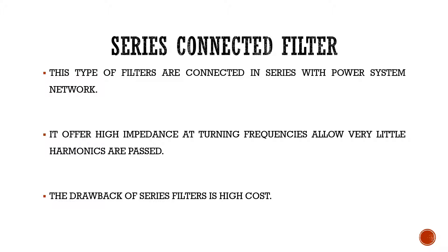However, the major drawback of the series connected filter is its cost — it is very high cost compared to that of shunt connected filter. It is also capable of compensating only lower order harmonics, because the number of series connected filters required will be very high for higher order harmonics. These are the major drawbacks of the series connected filter.